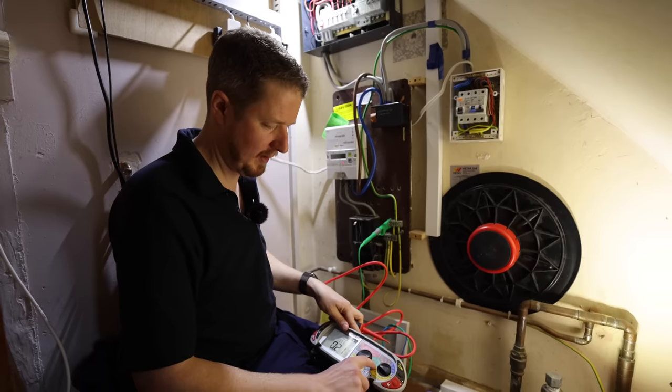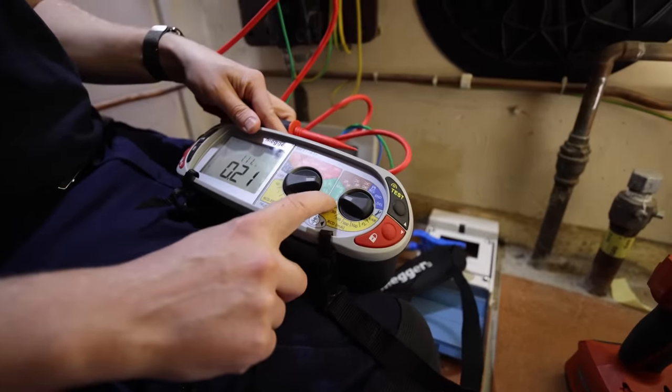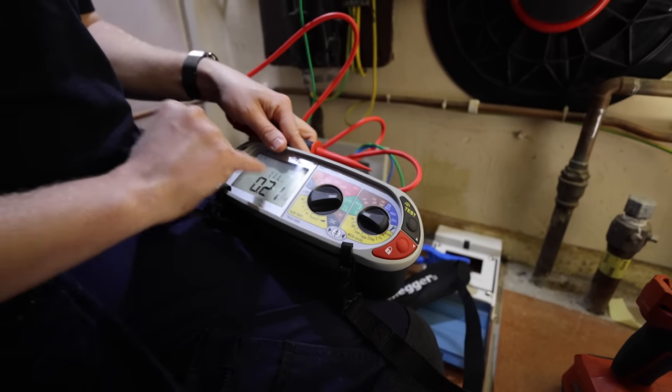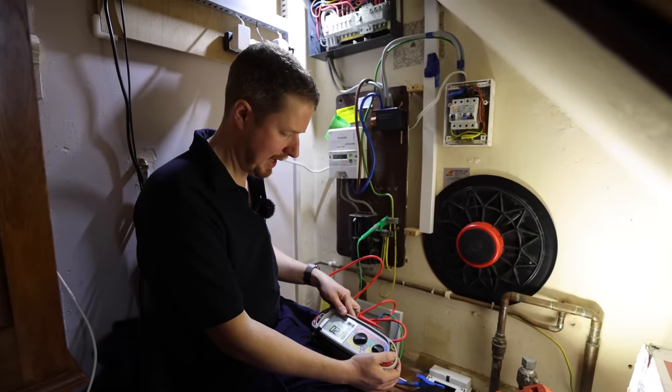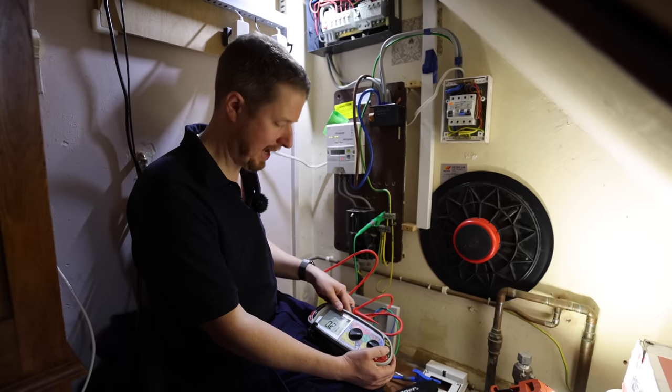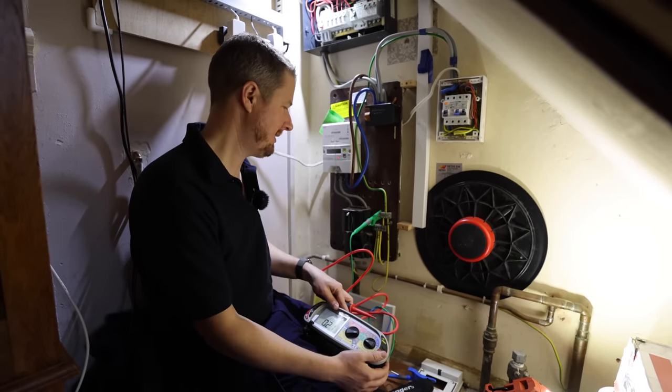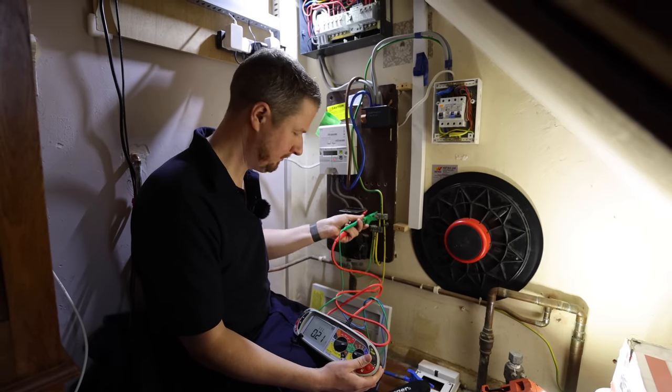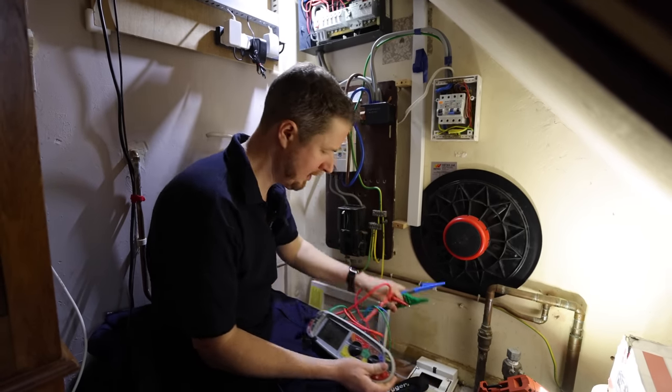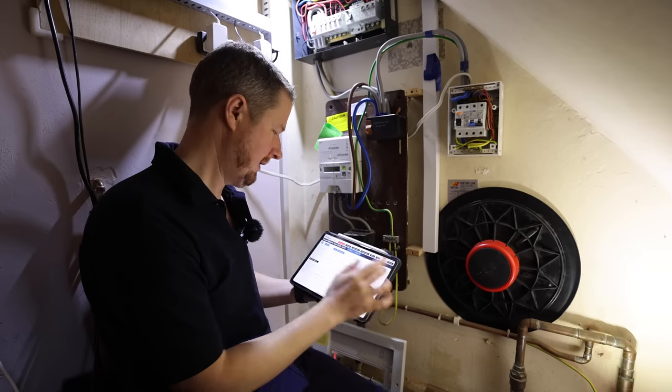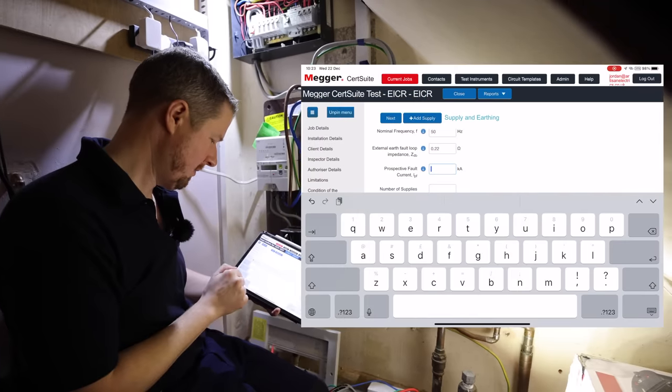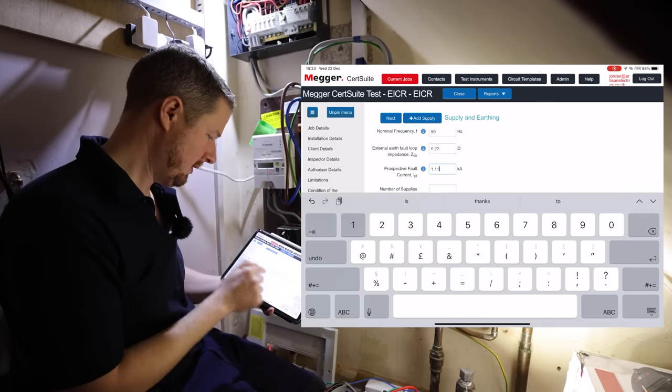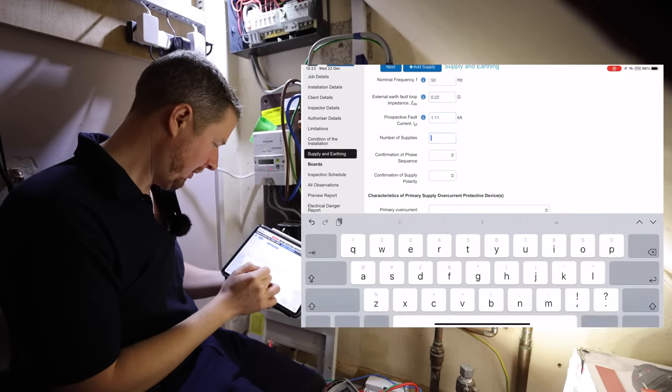Prospective fault current needs to be done with all the bonding conductors in place, so we'll connect that back now. So I've put it on the Z setting, and then it gives you the kA reading at the top. So we've got 1.11 kA, or in other words 1110 amps, is the maximum prospective earth fault current.